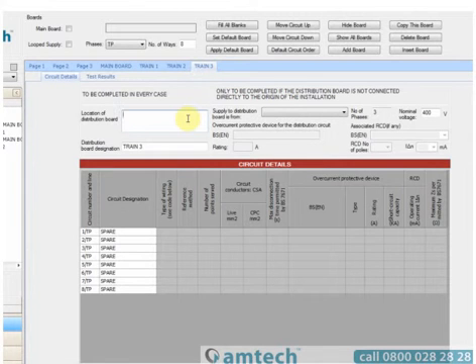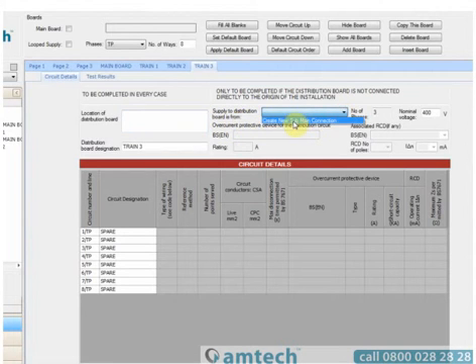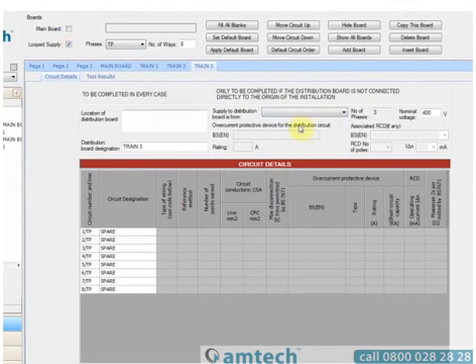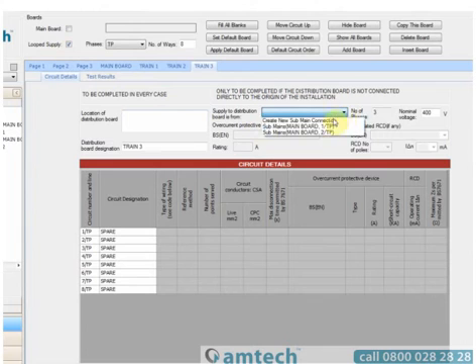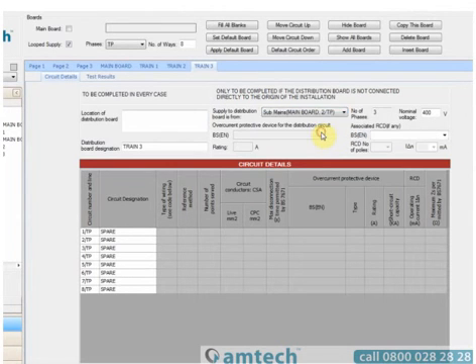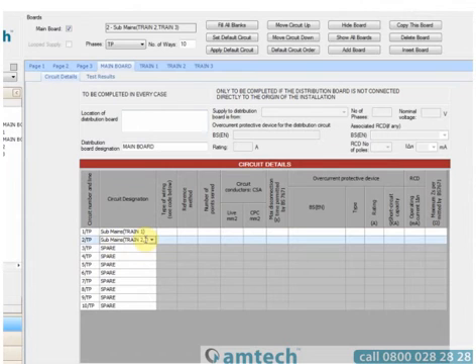Train 3 is a looped board. This means that it shares its protection with another board on the system. If I were to select Supply to Distribution Board is from now, I'd only see the option to create a new sub-main wizard. If I select Looped Supply and then drop it down, it will allow me to connect to either of these boards to show that it is looped alongside that one. Let's loop it with Submains Main Board 2TP. That connection has now been made, and if I return to the main board, I can see that I now have a Submains to Train 2 and to Train 3.